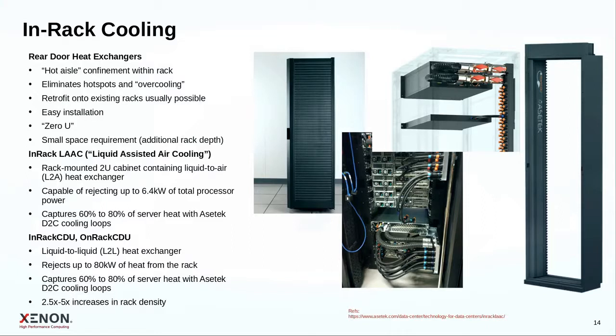Another interesting solution we installed recently as a temporary solution is in-rack liquid-assisted air cooling, where you have the liquid cooling solution in the server. The tubing comes out the back and goes into the manifolds, and then the manifolds go into a 2U unit with a huge heat exchanger in there. That way we don't need so many small heat exchangers in the system - we really just need a cooling block and the tubing in the server itself, then into the manifolds and into the in-rack unit.